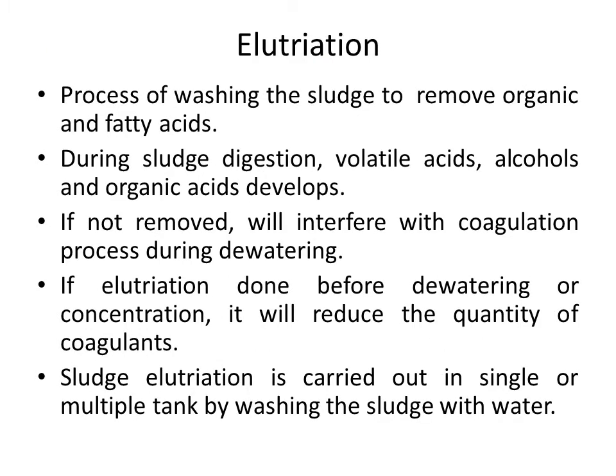Elutriation is a process of washing the sludge to remove organic and fatty acids. Normally during the sludge digestion process, volatile acids, alcohols, and organic acids develop within the digestion tank. If these acids and alcohols are not removed, they will interfere with the coagulation process during de-watering, since we add chemicals as a coagulant during de-watering.